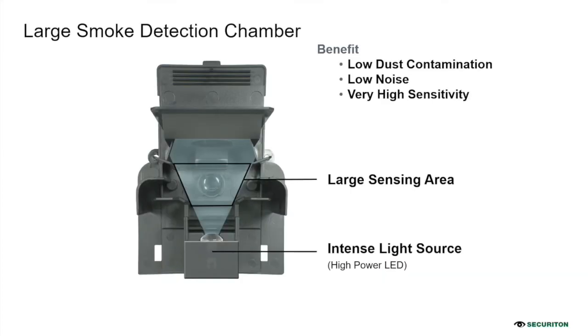Another good feature with our aspirating smoke detector is the large smoke detection chamber. Why is this important? Because the sucked air is continuously sampled for its contents, and whenever the defined threshold is exceeded, we can have different alarms. The large chamber allows us to sample more air, due to a large sensing area, for quick and early detection. That is one of the best parts of our aspirating smoke detectors.